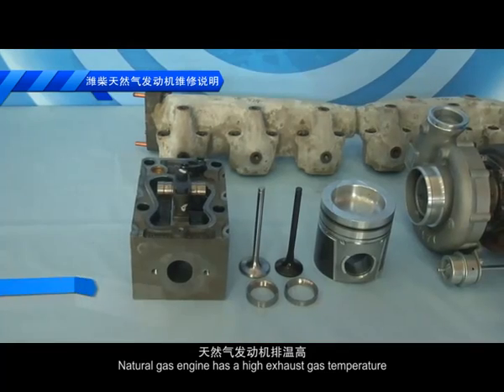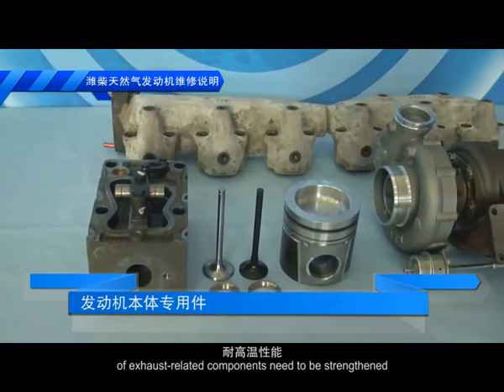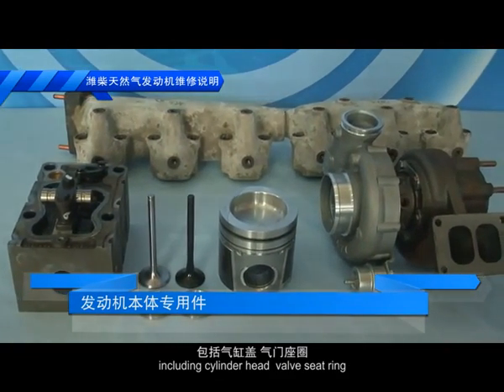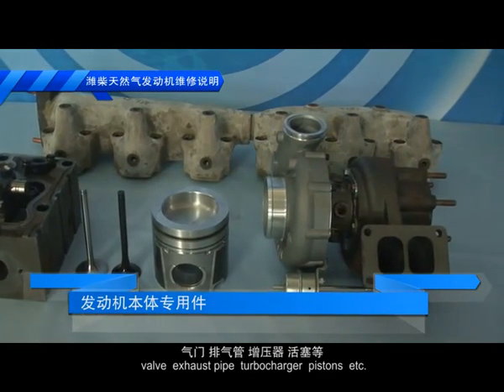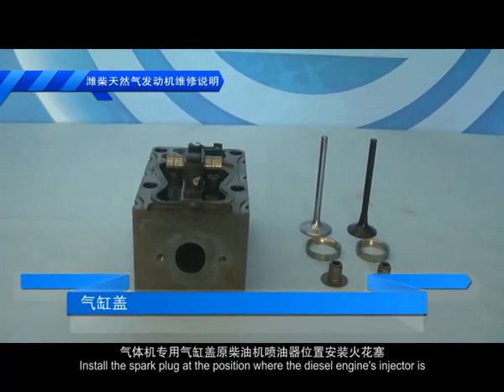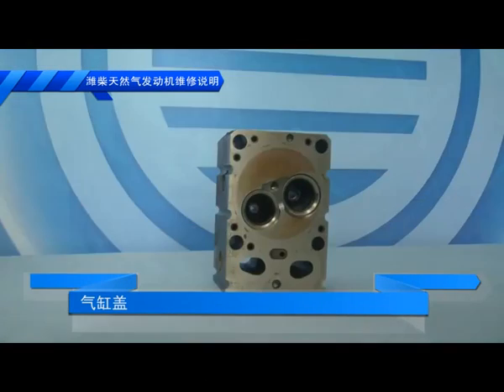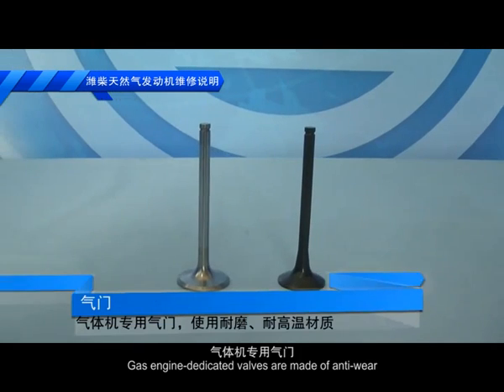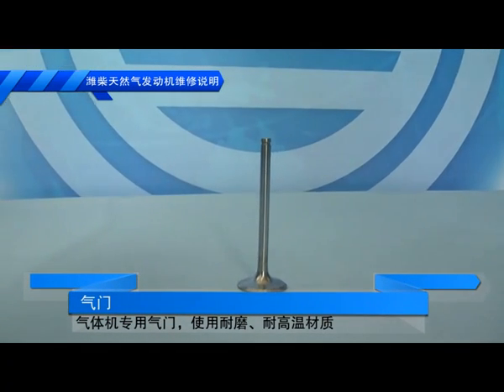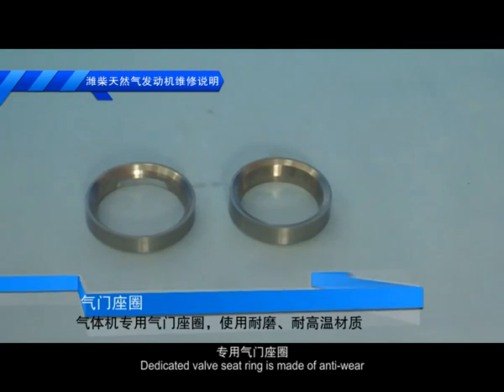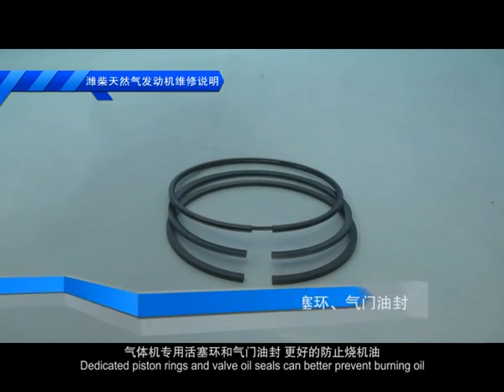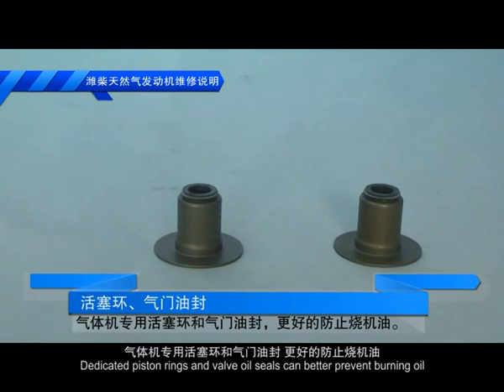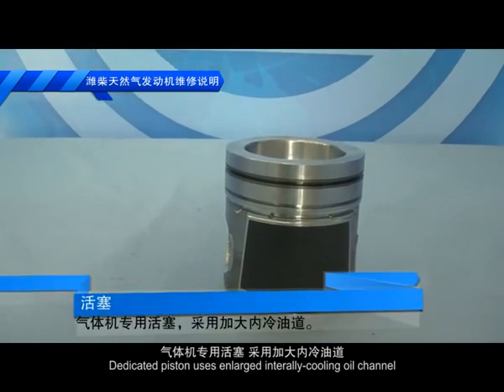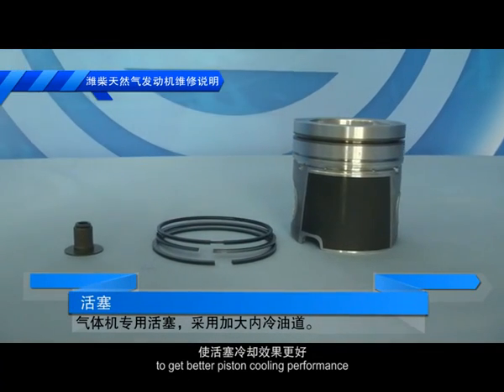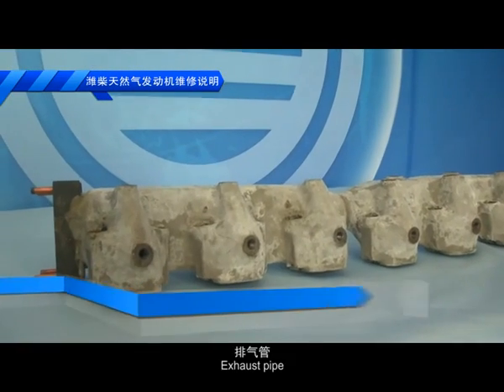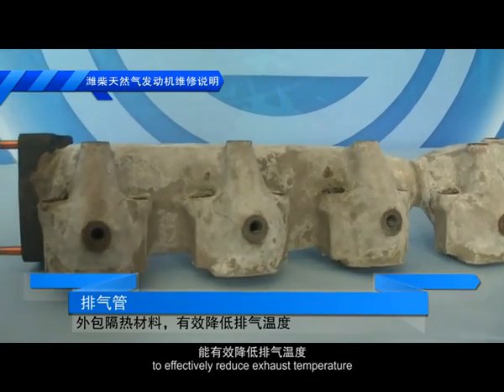The natural gas engine has a high exhaust gas temperature, therefore the temperature performance of exhaust-related components needs to be strengthened, including the cylinder head, valve seat ring, valve, exhaust pipe, turbocharger, pistons, etc. Install the spark plug at the position where the diesel engine's injector is. Gas engine dedicated valves are made of anti-wear and high-temperature proof materials. The dedicated valve seat ring is made of anti-wear and high-temperature proof materials. Dedicated piston rings and valve oil seals can better prevent burning oil. The dedicated piston uses an enlarged internal cooling oil channel to get better piston cooling performance. The exhaust pipe is wrapped with one layer of insulating material to effectively reduce exhaust temperature.